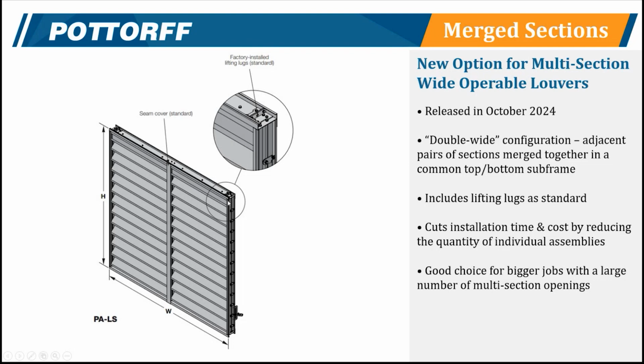This configuration comes with factory-installed lifting lugs as standard, since it's a larger assembly, to help with lifting and handling. It goes up to 96 by 96, or up to 120 by 96 for a louver with no jamb seals, at 60 inches wide per section. We're grafting two of those together, so it can be quite a large assembly shipping out as one piece.